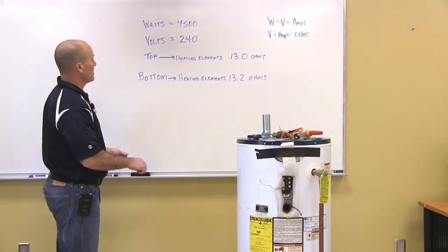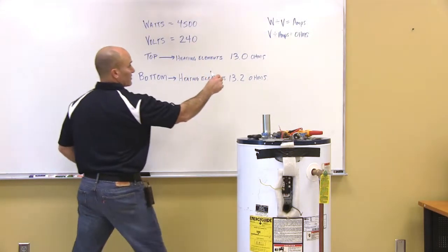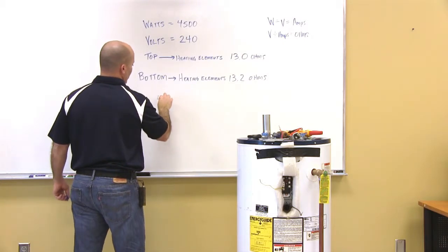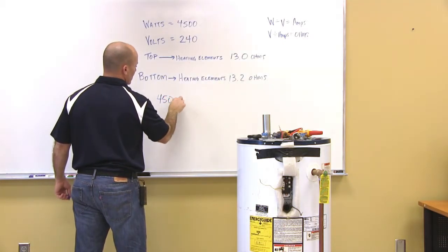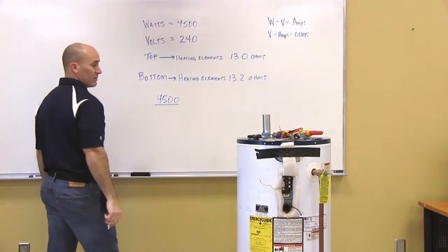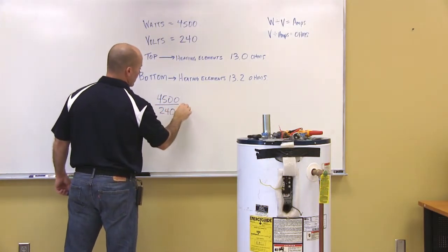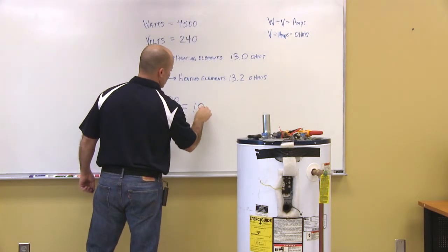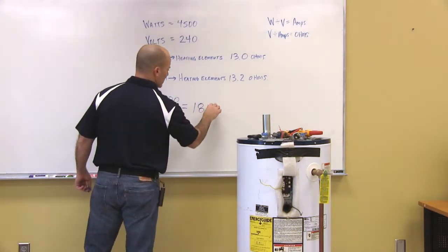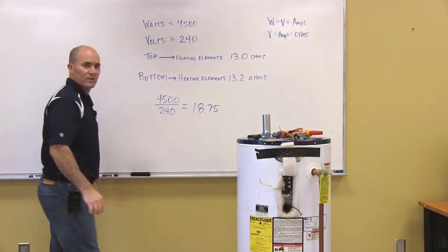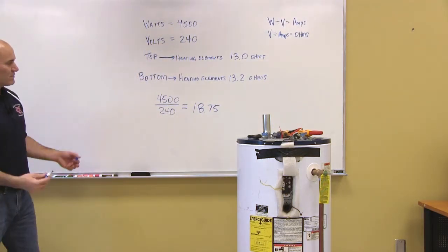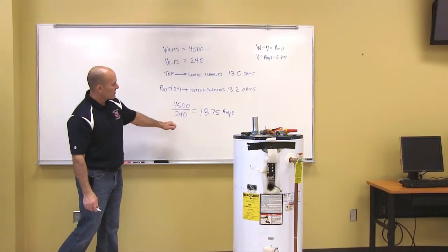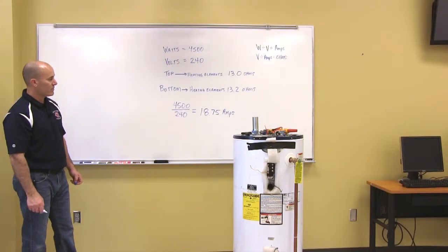So let's do the math. Here's some formulas for you up here: watts divided by volts equals amps. So 4500 divided by 240 equals 18.75. That's my amps, so I just found my amps, 18.75 amps, is our reading.